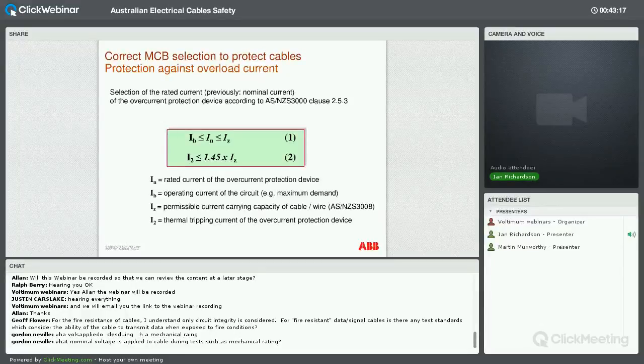In AS/NZS 3000, which I'm sure you're all very, very familiar with, in one of the clauses, they give a couple of very simple formulas. With this, we've got an operating current, which is the IB value on the top line. Then you have the rated operating current of the overcurrent protective device, which is our circuit breaker, and that is then below the permissible current carrying capacity of the cable.